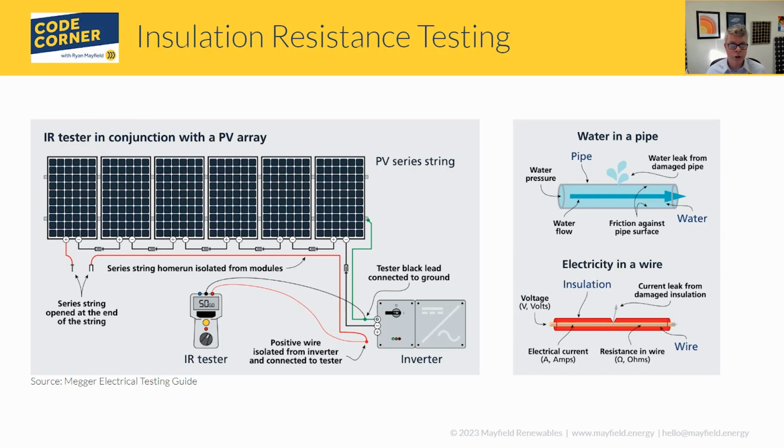You have a known voltage and a known current, so it can calculate the resistance. If you get a reading back that's a very large resistance, that tells you your conductor is in really good shape. If you get a resistance that comes back very, very low, then you potentially have problems in that conductor, and maybe you need to replace it or investigate it some more.